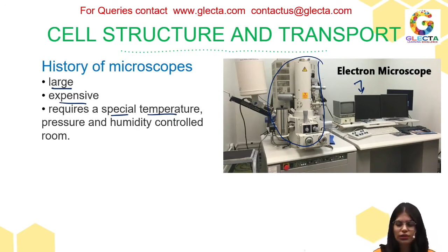The third thing, which is very, very important, is that the temperature, the humidity, the pressure in the room, everything would have to be controlled. So whatever high-tech movie you can think of, there's a room that has a panel, and that panel is set up for what temperature is going to be there, what the pressure and the humidity in the environment of the electron microscope is. If that changes, your images will not come out as they were supposed to, or maybe the entire setup would shut down. So that is something you have to make sure of.